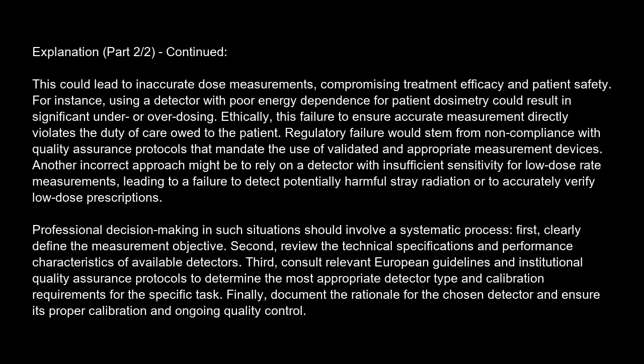Another incorrect approach might be to rely on a detector with insufficient sensitivity for low-dose rate measurements, leading to a failure to detect potentially harmful stray radiation or to accurately verify low-dose prescriptions. Professional decision-making in such situations should involve a systematic process. First, clearly define the measurement objective. Second, review the technical specifications and performance characteristics of available detectors. Third, consult relevant European guidelines and institutional quality assurance protocols to determine the most appropriate detector type and calibration requirements for the specific task. Finally, document the rationale for the chosen detector and ensure its proper calibration and ongoing quality control.